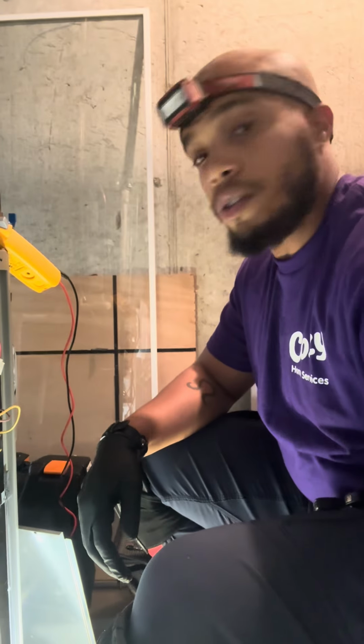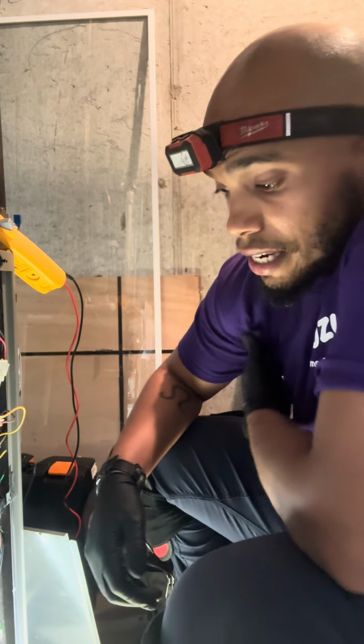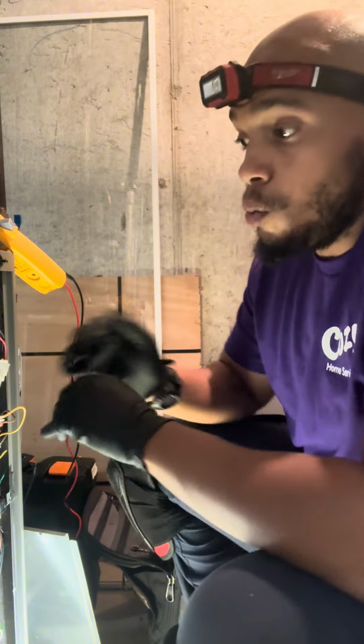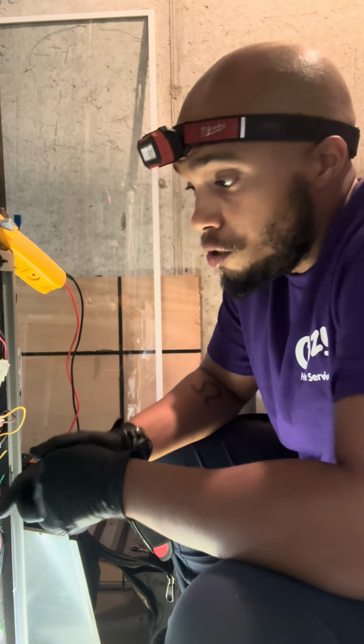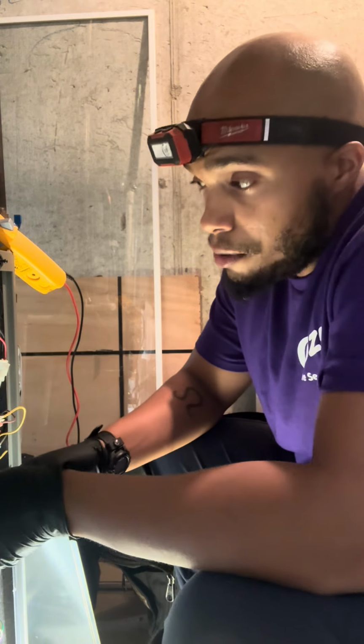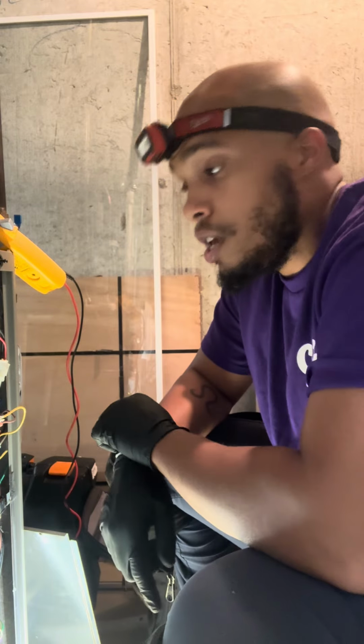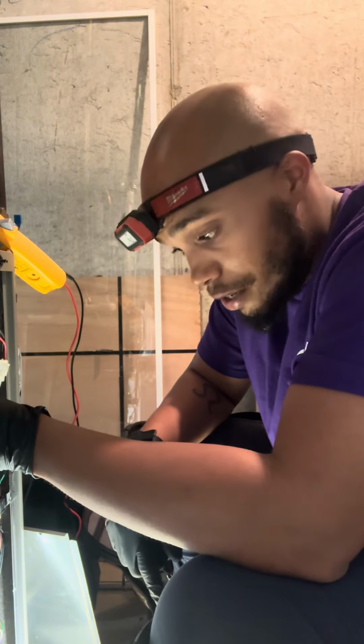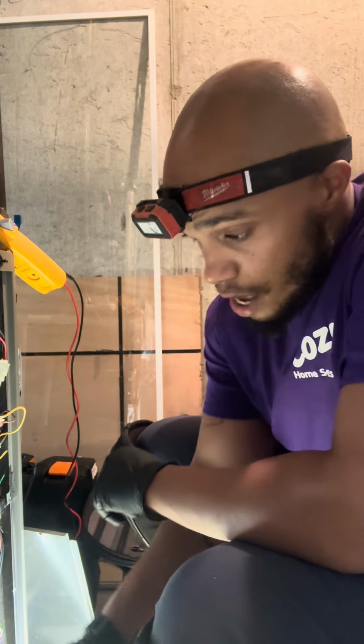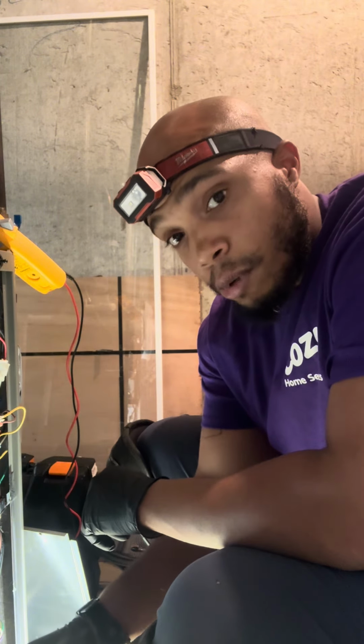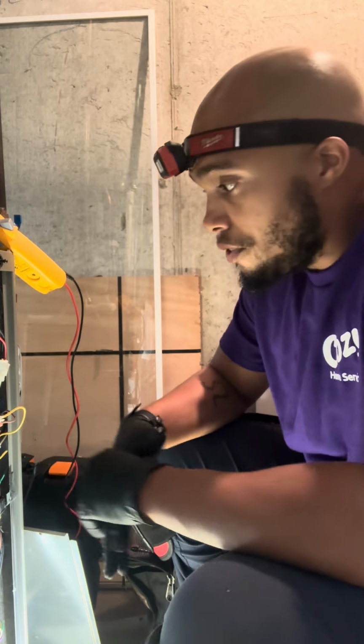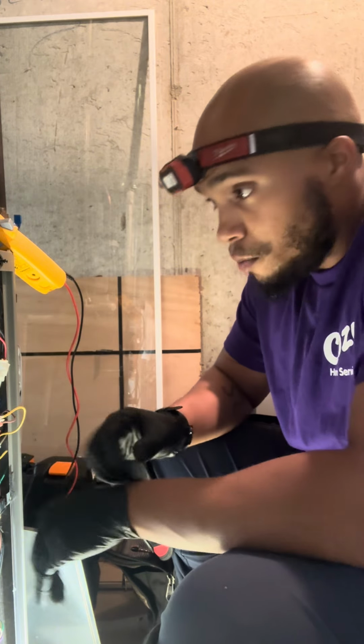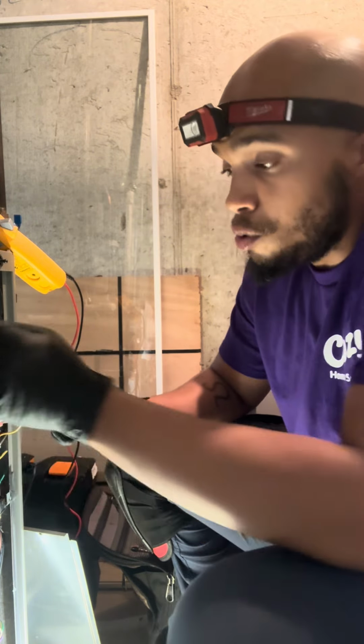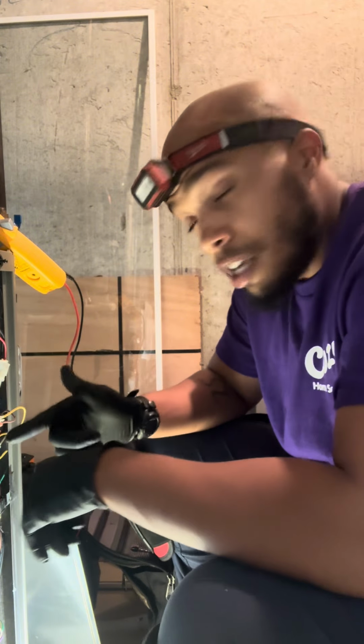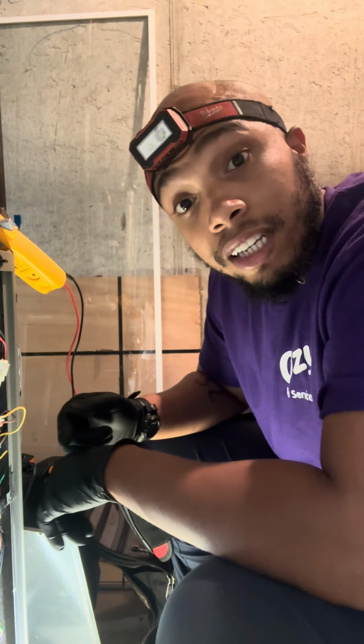As far as this furnace goes, those are the main things that need to be addressed when you are breaking the furnace down. You need to check the burner box, you need to clean the flame sensor, you need to check all the capacitors, you need to make sure all the drain lines are clear, and you need to make sure your electricals are secured and your blower wheel is clean and there's no play in the shaft. So now that we've established all of that, we checked our heat exchanger, I'm going to put things back together. I'm gonna get out my shop vac and we're gonna do some cleaning.